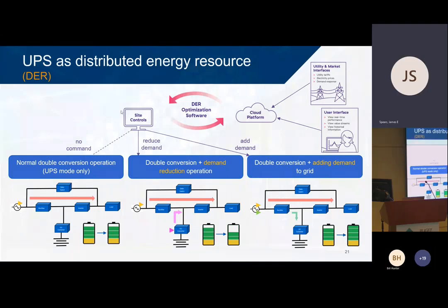So here's a little slide that is not animated, but it shows the UPS being used as a distributed energy resource in three modes of operation. The one on the far left is traditional UPS operation. Power flows from the utility input on the left, where the little orange arrow is, and follows the red arrow right straight through the machine and out to the critical load. Power always flows in the same direction, from input through the rectifier, converted to DC. That tops off the battery, and the inverter takes that same DC and rebuilds an AC output, sends it out to the critical load, the way UPSs have worked since the 1960s.